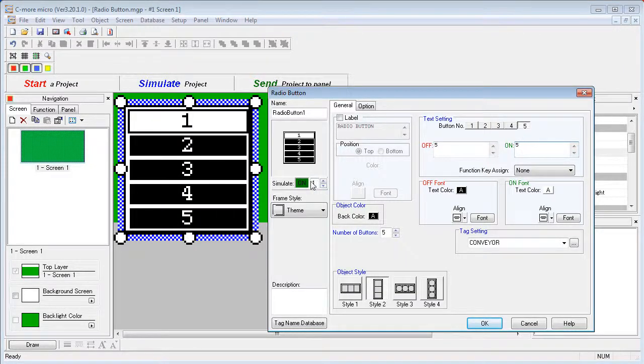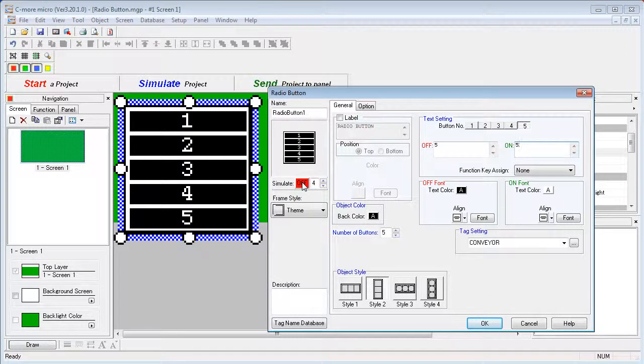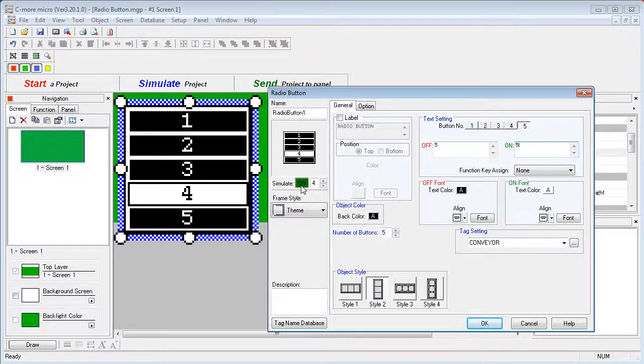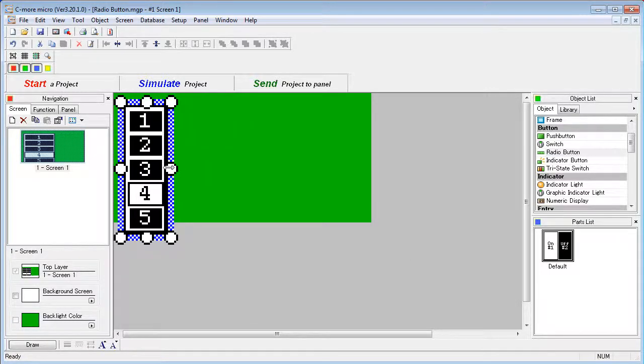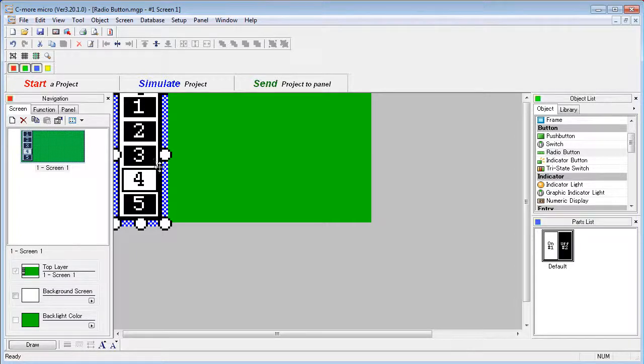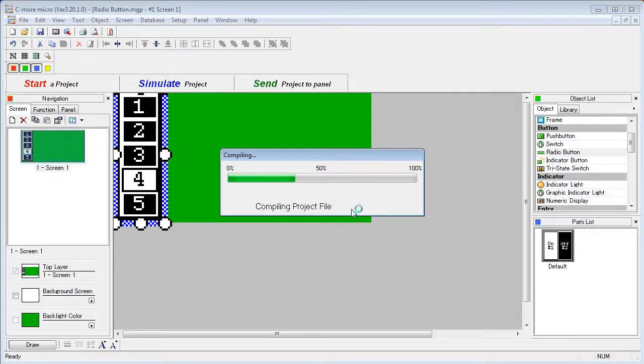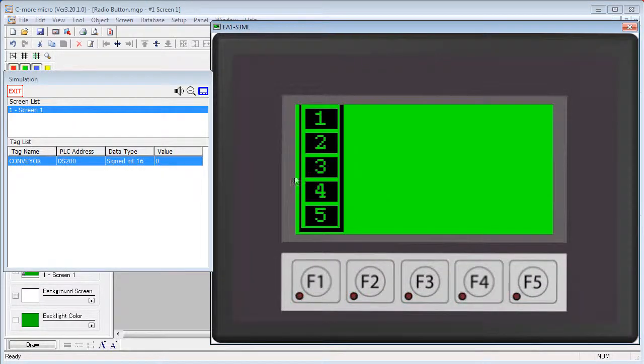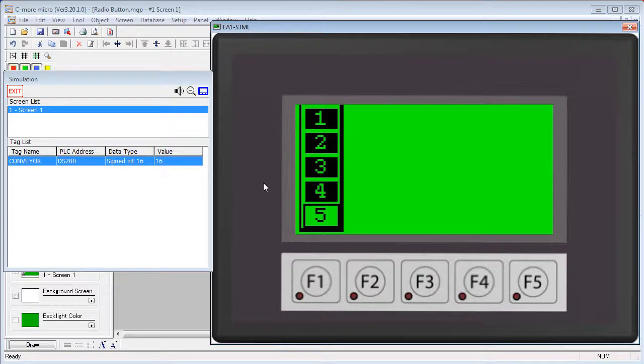You can test this button any time you want by using the simulator. Select the button you want to test and you can see what the end result is going to look like. Hit OK, resize the button, place it on the screen where you want it, and hit simulate. Save the project and up pops our simulator. Just as we saw earlier, these buttons are modifying individual bits in this conveyor tag. If I press 1 I get a 1; pressing 5 gives me a 16.